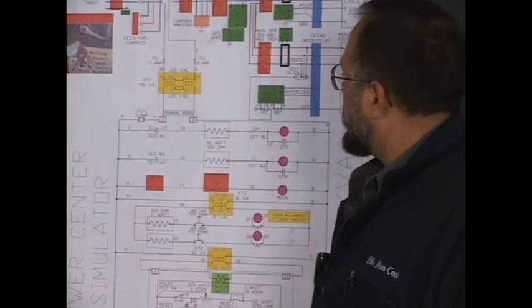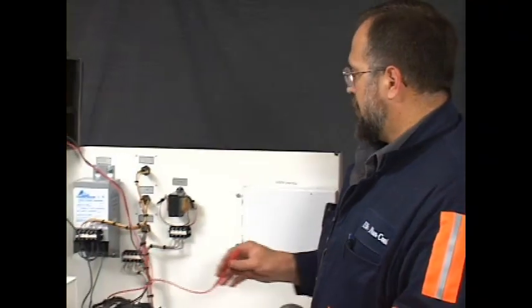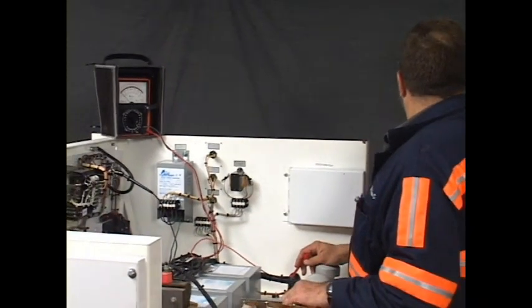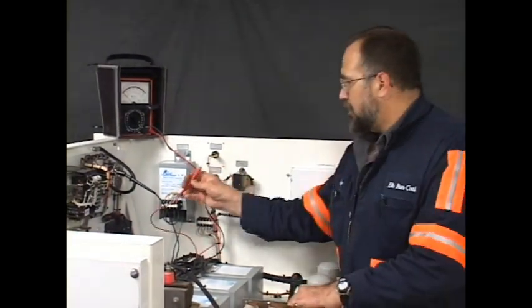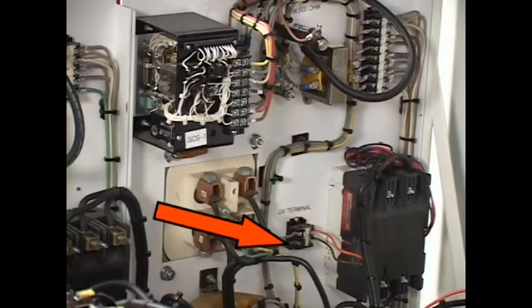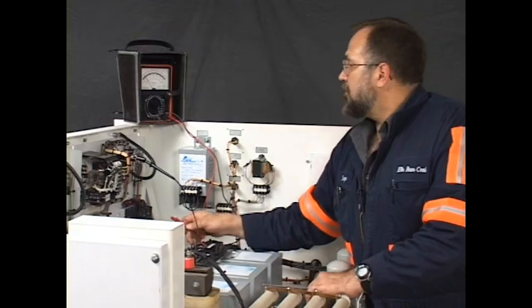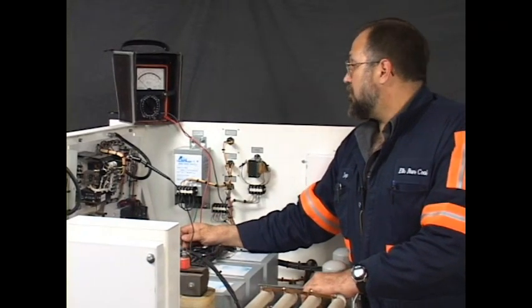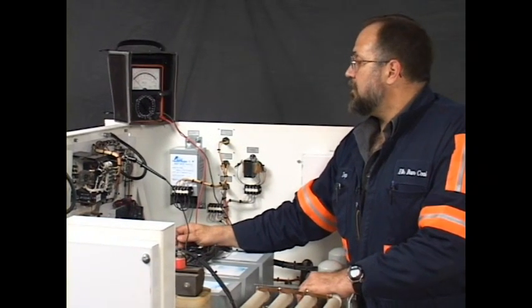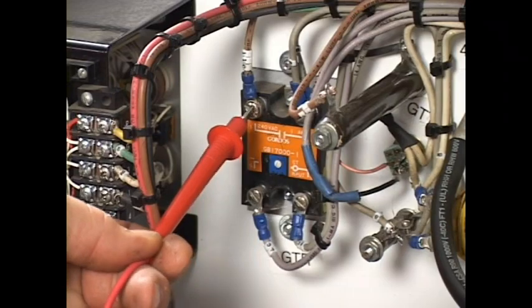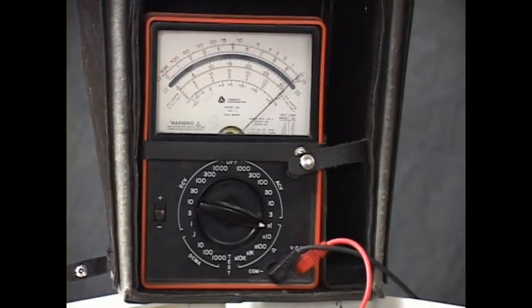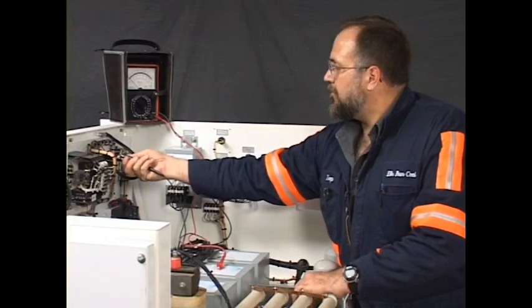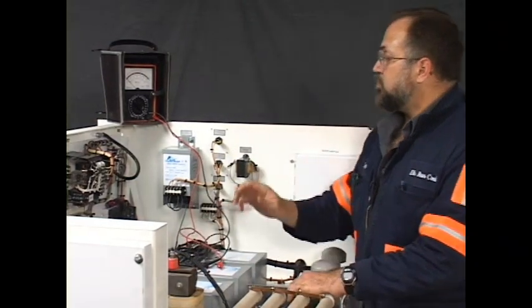I'm going to leave my black lead attached on the load side of that and continue to follow this to the UVR, reading wire number 11. The next point it goes to is the UVR terminal block down on the bottom here, and it reads good. Okay. Wire number 11 also should read to the GTR contacts, and it does. Okay, there you have it. That's how the circuit should properly read.